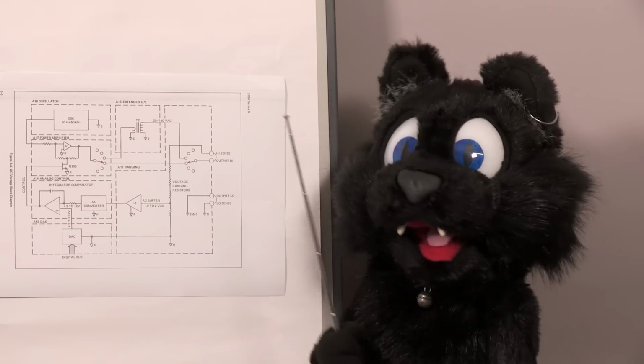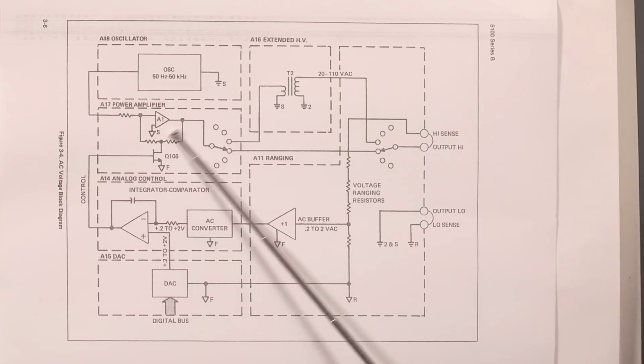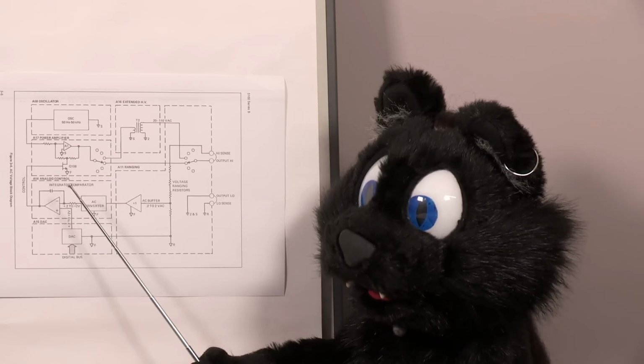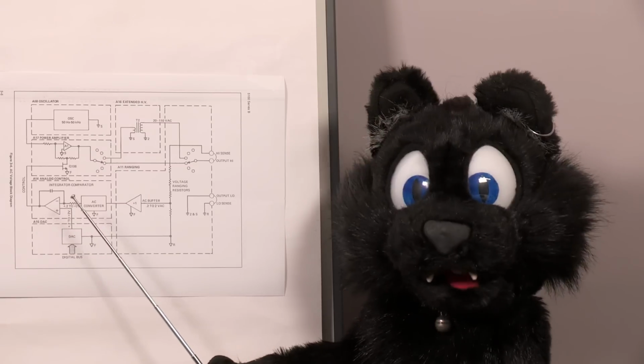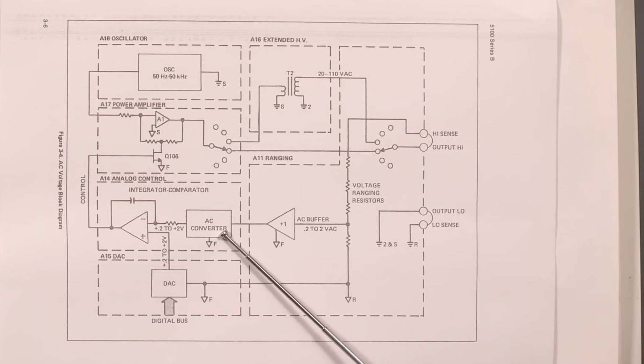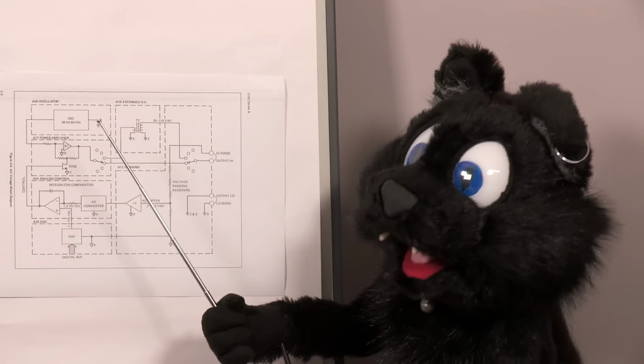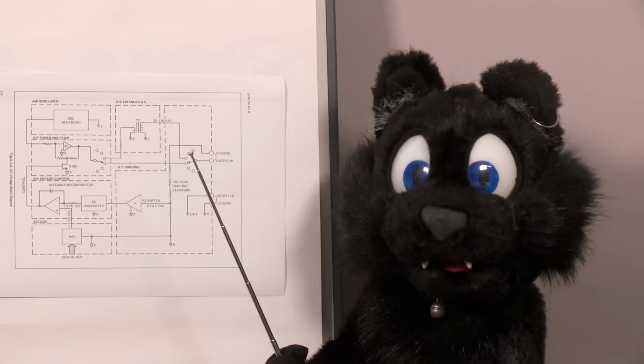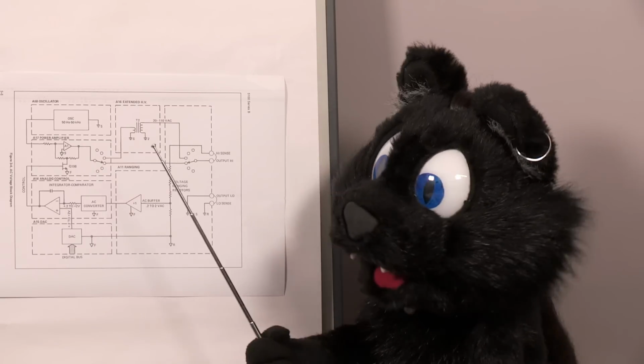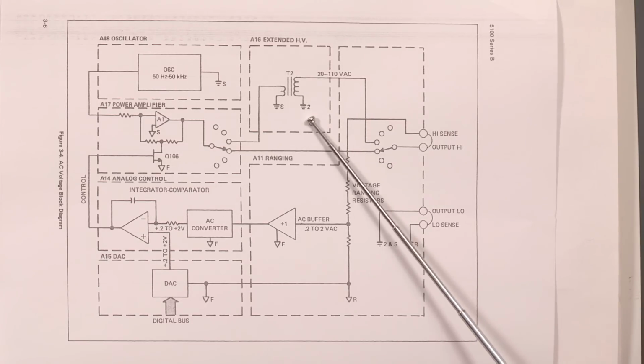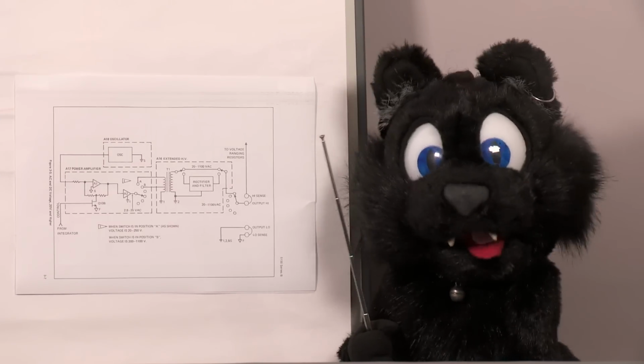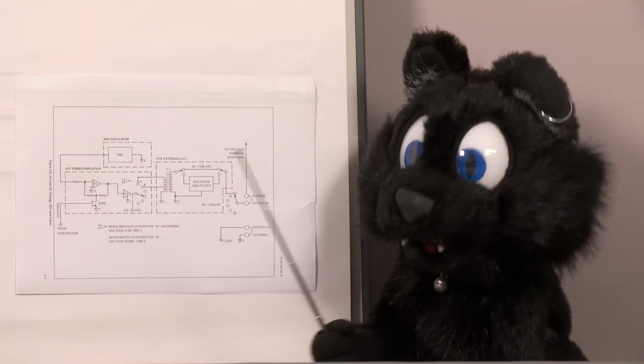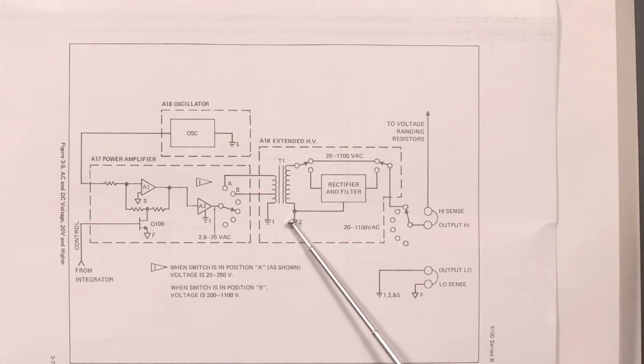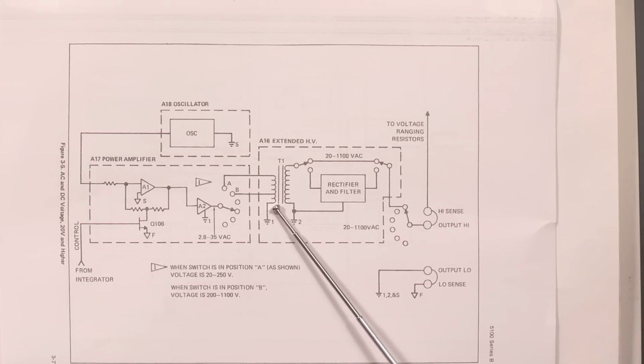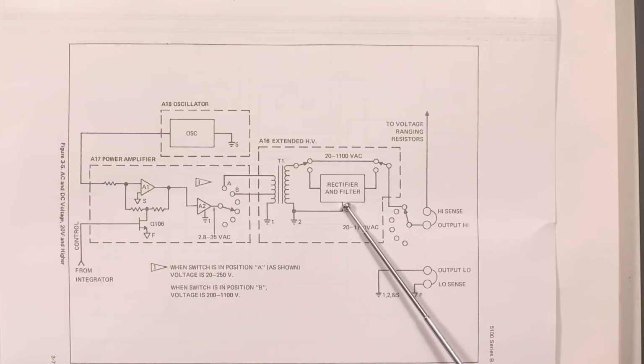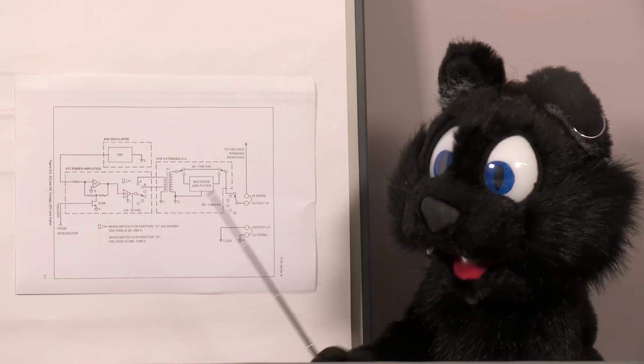AC voltage is created from the oscillator PCB, amplified by the same power amplifier. The gain and thus absolute output value is controlled via the analog control feedback loop again, but this time there's an integrator put into play to convert the output AC to DC first. The oscillator can provide a discrete set of frequencies only, but it does provide a pretty nice sine wave output. For higher voltages, there's the extended high voltage PCB that acts as a step-up transformer. Now, when asking for 20 to 1100 volt AC, the high voltage board uses the big transformer instead of the small toroidal one. It has two primary coils to aid in different ranges again, and also a pretty standard rectifier and filter circuit for making DC output. The rest is the same as for the low-range AC configuration.